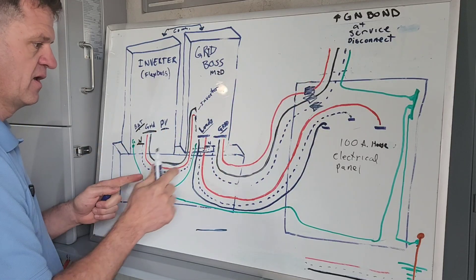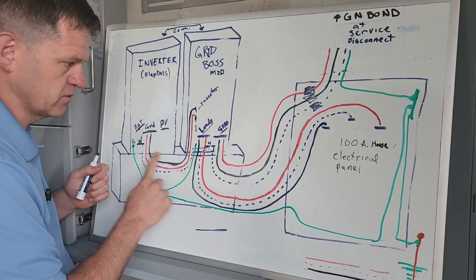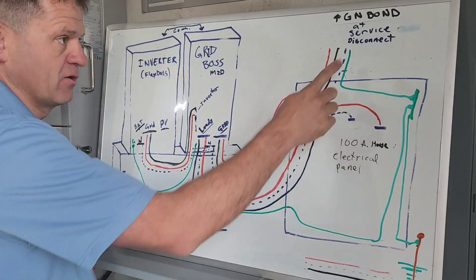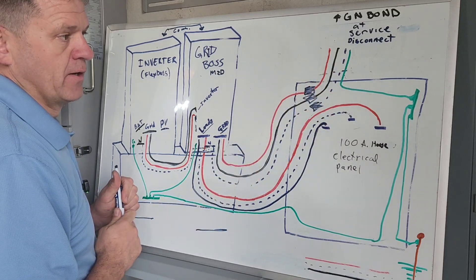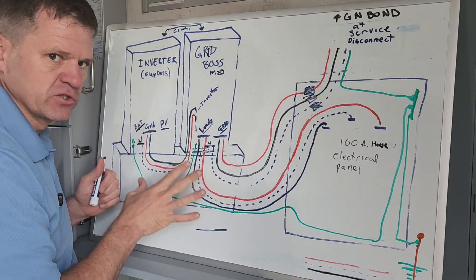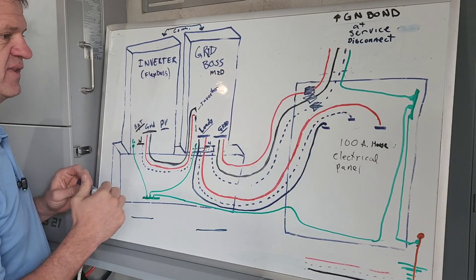These connections go all the way out and it sees this ground-neutral bond connection. So these have continuity here. So because all the neutrals are all connected together, and my grounds are all connected together, they are all connected through that one ground-neutral bond. So I don't need to make like an extra ground-neutral bond as part of that. So if you are using your Grid Boss as your service disconnect, there are some jumpers where you can add the ground-neutral bond into the Grid Boss.